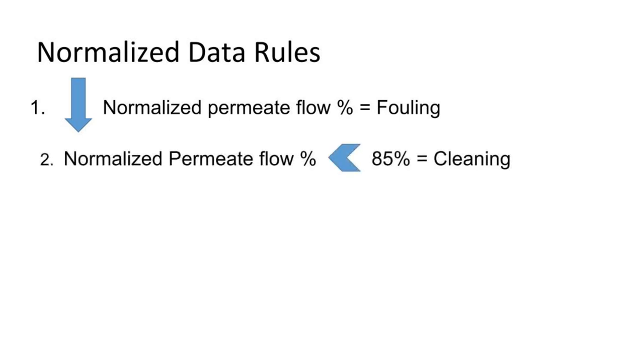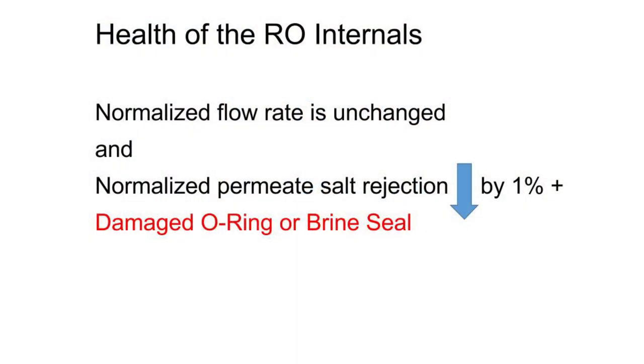If normalized permeate flow percent is less than 85%, the RO membranes should be cleaned. A combination of higher normalized permeate flow percent and lower normalized rejection percent indicates RO membrane damage. If normalized permeate flow percent is greater than 110 and normalized rejection percent decreases more than 1%, the RO membranes are damaged and should be replaced. If the normalized permeate flow percent is relatively unchanged and the normalized rejection percent decreases more than 1%, additional troubleshooting is needed to determine which O-rings are damaged.